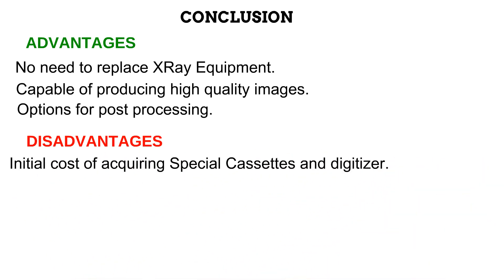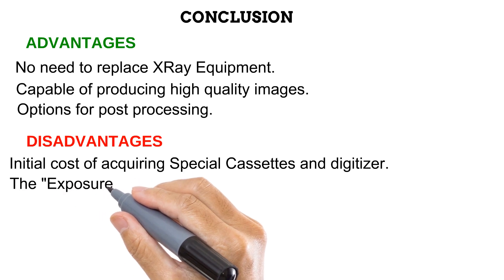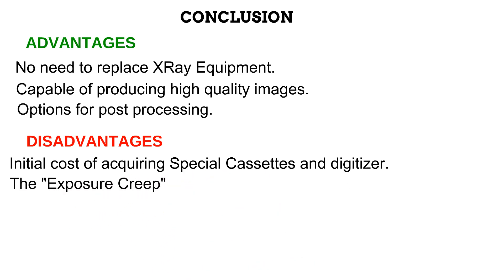However, the disadvantages of computed radiography include the initial cost of acquiring the special cassettes and digitizer, which are pretty expensive. The second disadvantage is a phenomenon known as exposure creep. Computed radiography produces high-quality images and allows manipulation of images even when wrong exposure factors have been selected. While this is supposed to be a good thing, in the wrong hands it is dangerous. A radiographer who is careless with selection of exposure factors and knows images can be manipulated to become acceptable is likely to use too high exposure factors on patients, exposing them to more than needed radiation.